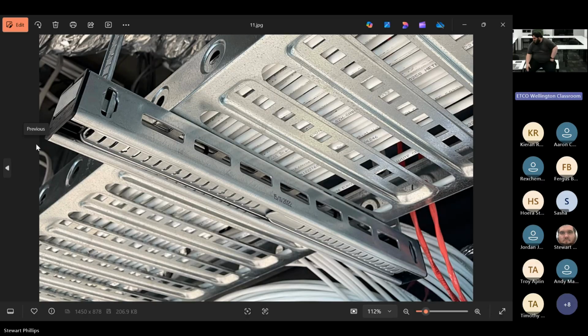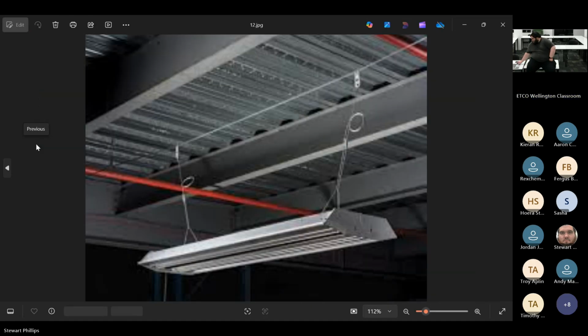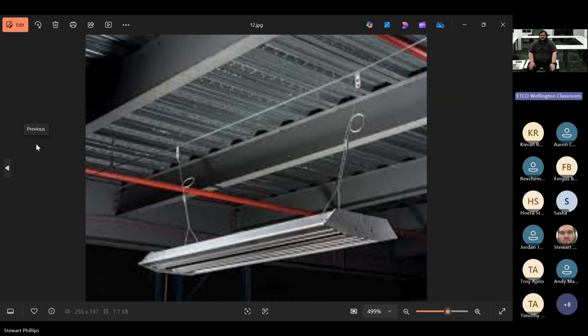Cool. Just a better shot of the underside of the Unistrut for the cable tray. I'm not 100% sure what kind of hanging system they're using there, but usually we would be using threaded rod with nuts and bolts. Cool. Catenary hanging systems. So what do we need to be aware of with catenary systems?